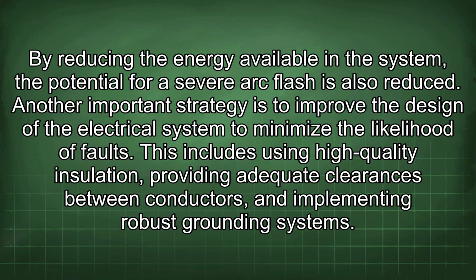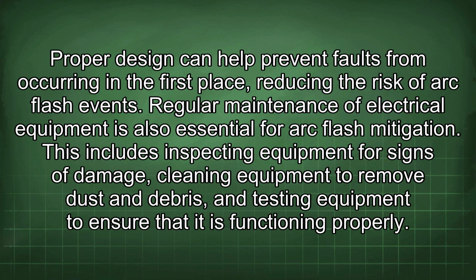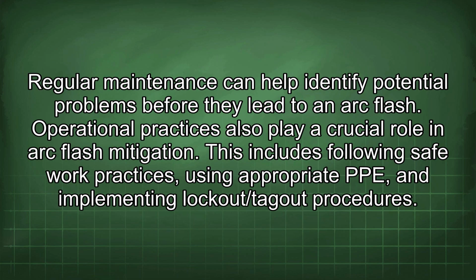Another important strategy is to improve the design of the electrical system to minimize the likelihood of faults. This includes using high-quality insulation, providing adequate clearances between conductors, and implementing robust grounding systems. Proper design can help prevent faults from occurring in the first place, reducing the risk of arc flash events. Regular maintenance of electrical equipment is also essential for arc flash mitigation. This includes inspecting equipment for signs of damage, cleaning equipment to remove dust and debris, and testing equipment to ensure that it is functioning properly. Regular maintenance can help identify potential problems before they lead to an arc flash.